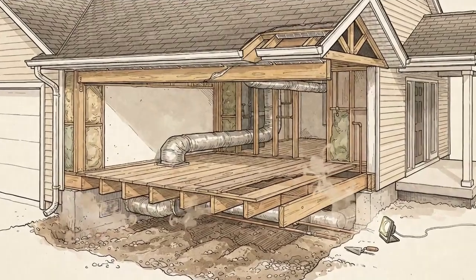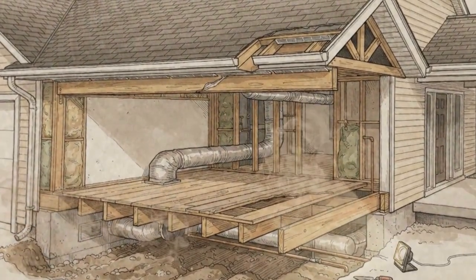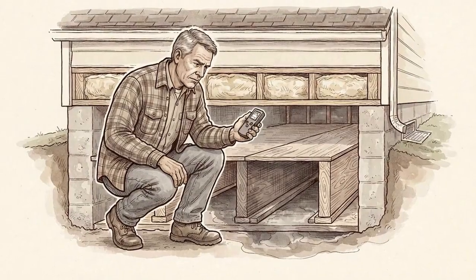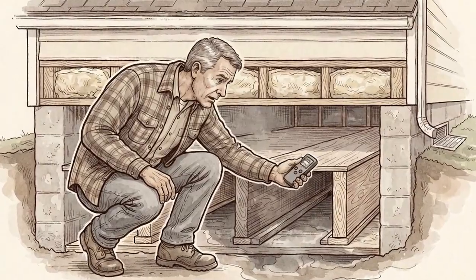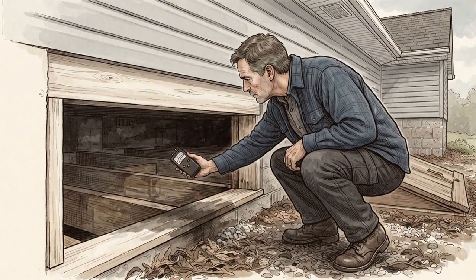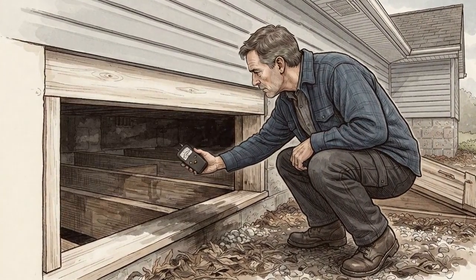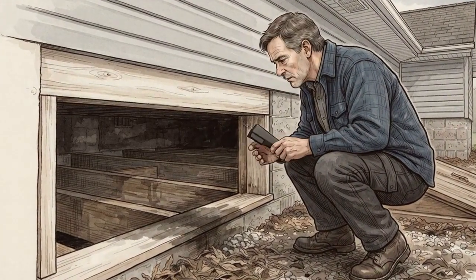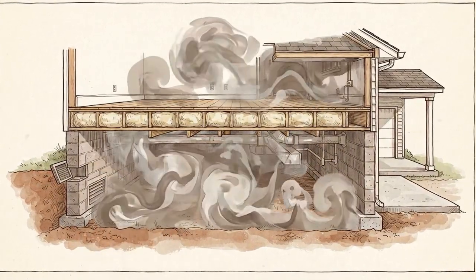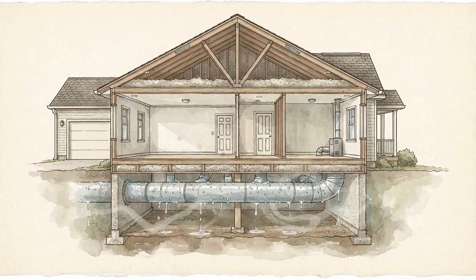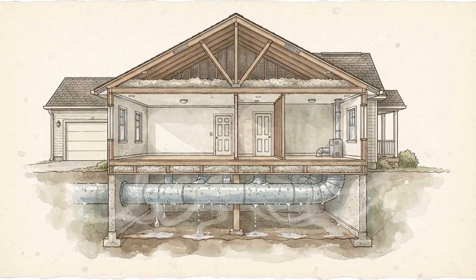Building Science Corporation field data from vented crawl spaces in climate zones 3 and 4 showed summer relative humidity regularly exceeding 90%. That happened on days when outdoor relative humidity was only 60 to 65%. The crawl space was wetter than outside. The vents made it wetter, and the soil kept it wet. At 90% relative humidity, you are 1 degree of surface cooling away from condensation at essentially any moment.